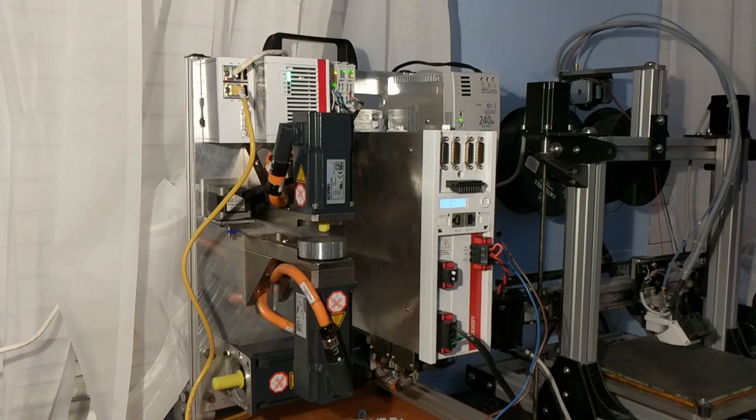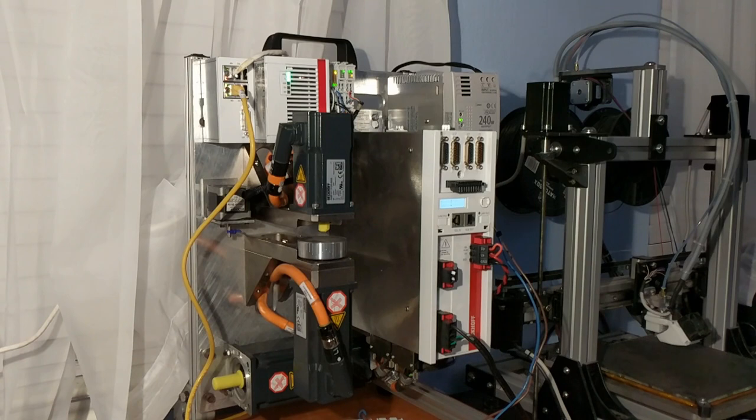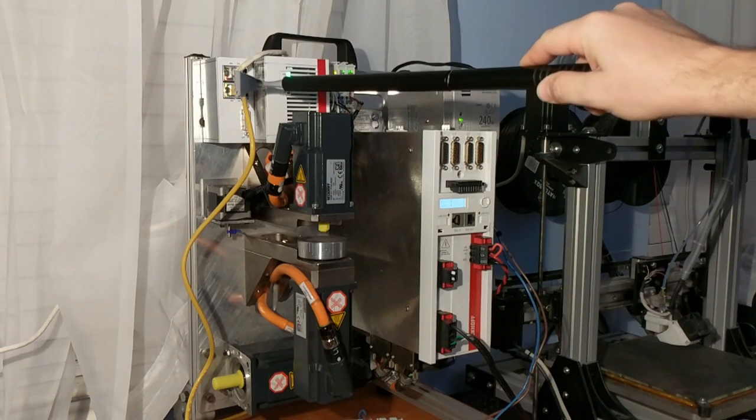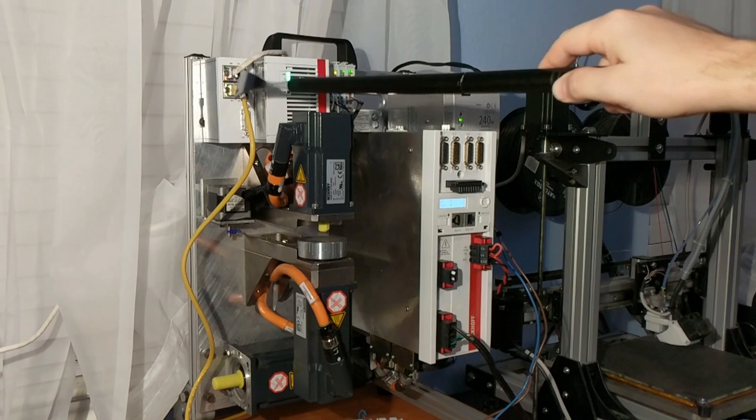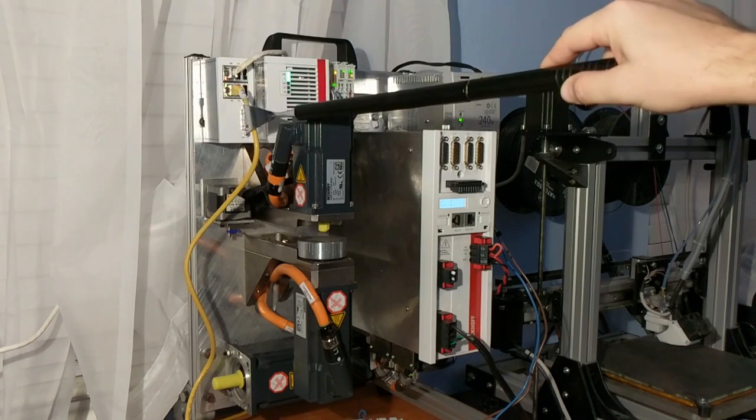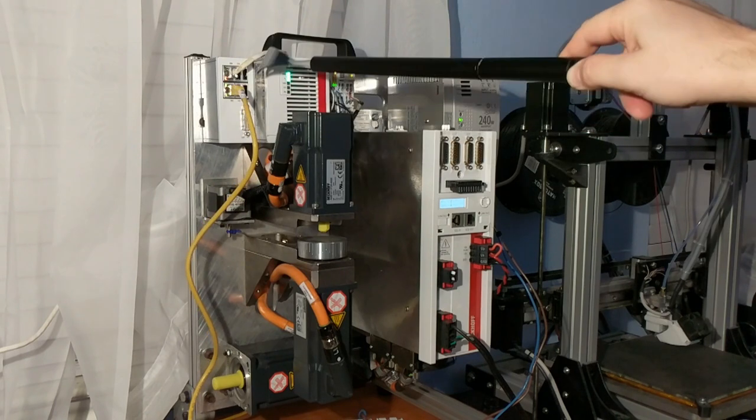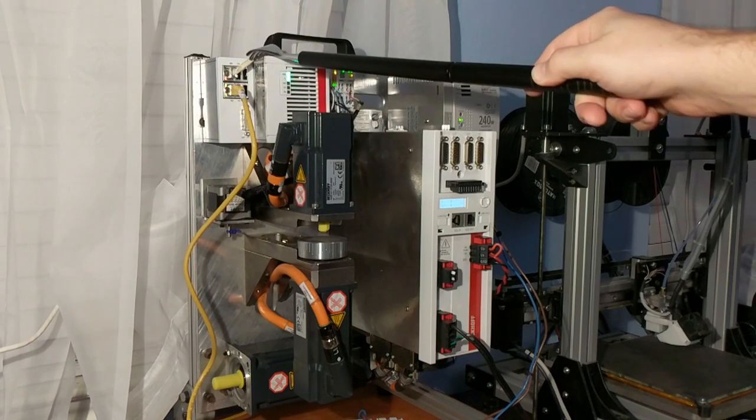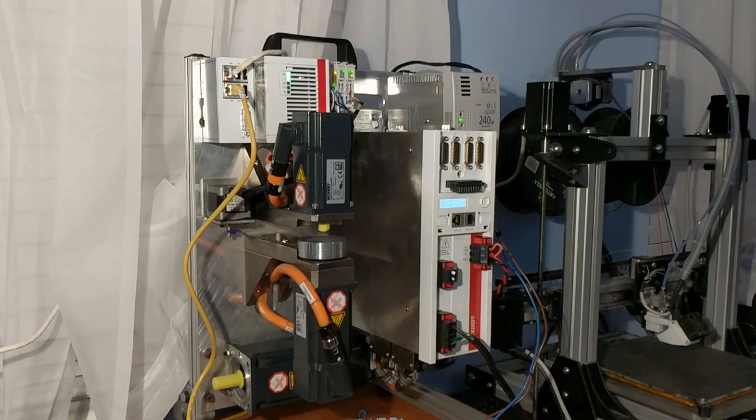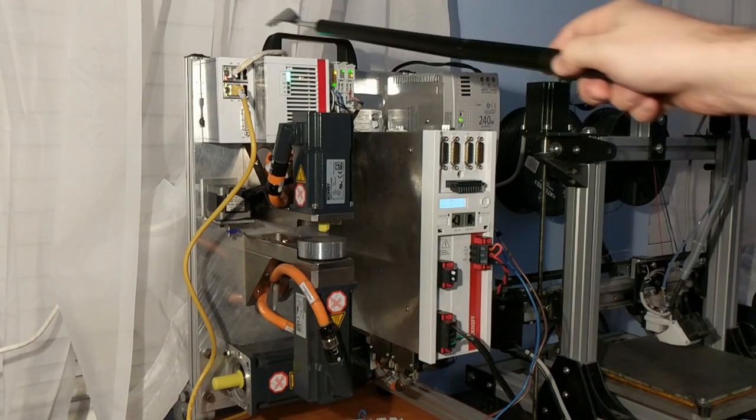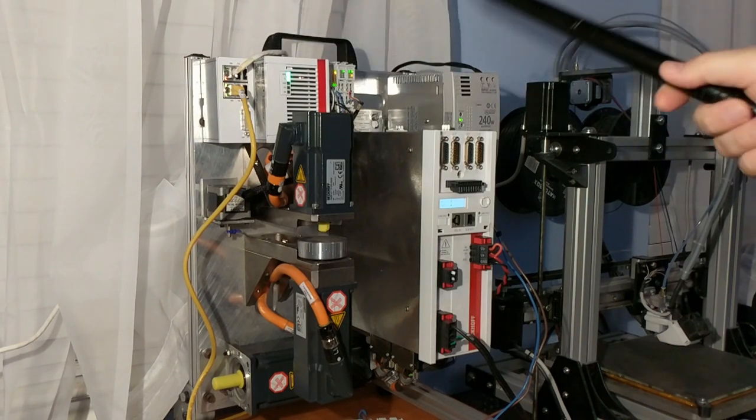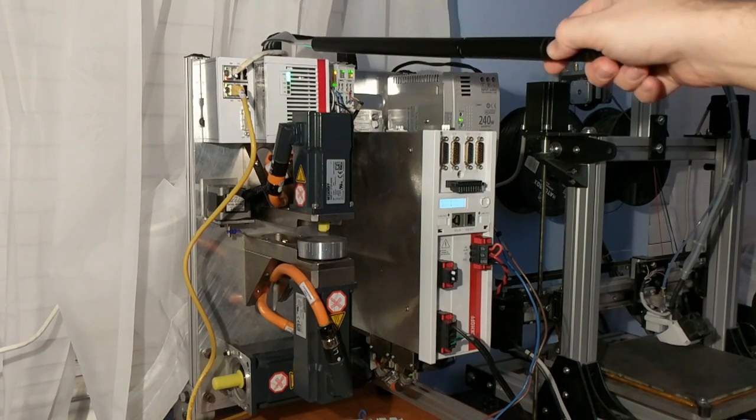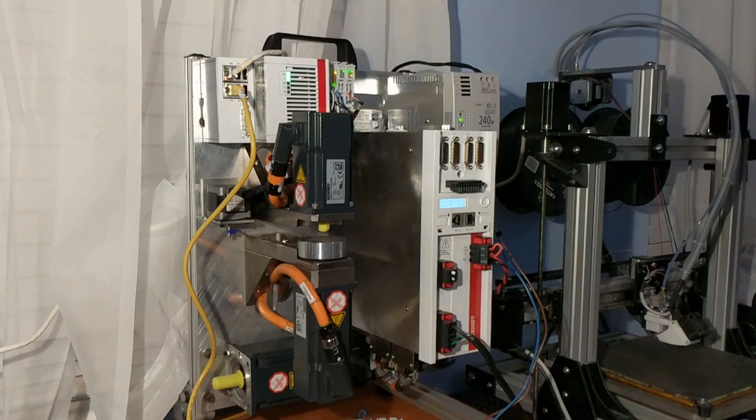We're back at the test bench here just for a second so I can show you how this EtherCAT system is wired up. These are both network cards on top of the PLC here on the left side. The yellow one we're dedicating to EtherCAT, whereas the other one is going to handle our regular TCP/IP networking. This is how we program the PLC. In practice it wouldn't necessarily need to be there, but modern days pretty much everybody runs some sort of networking to their PLCs.